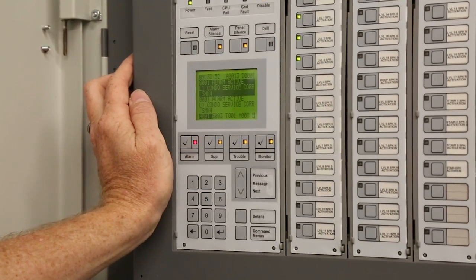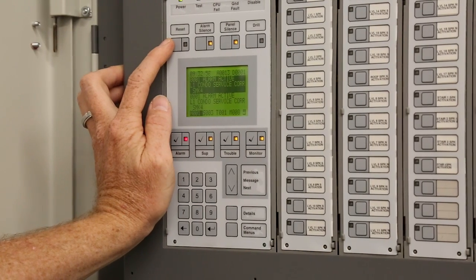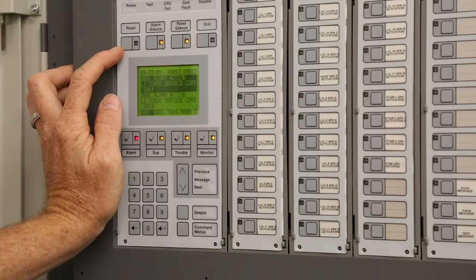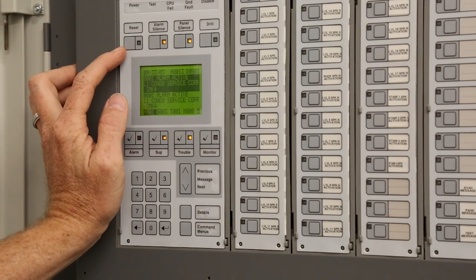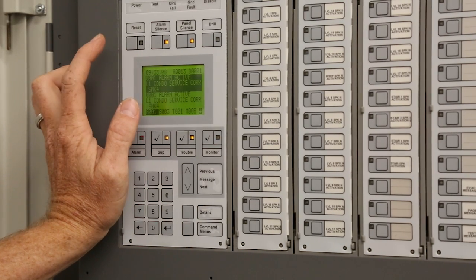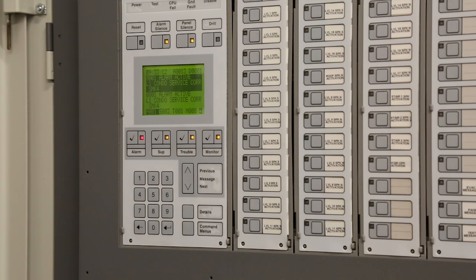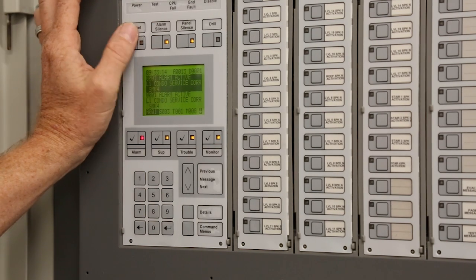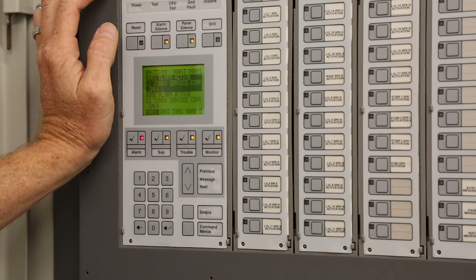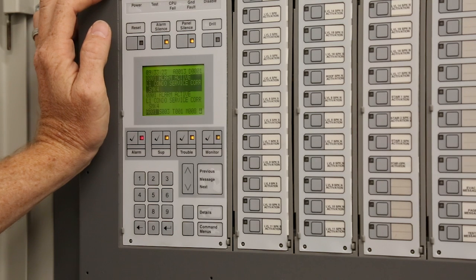You investigate it. There's no more smoke there. You can hit reset. Now, if that smoke detector still has smoke in it, it will not resound or refire if there's smoke in it, and it's still an alarm. Some systems you hit reset, all of a sudden it'll re-trigger and everything goes back in alarm. If that detector still has smoke and you hit reset, it'll just stay the way it is, okay? We'd have to bypass it or something. But what I'm getting at, it won't refire.